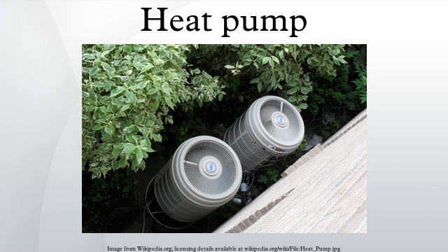Air source heat pumps are relatively easy and inexpensive to install and have therefore historically been the most widely used heat pump type. However, they suffer limitations due to their use of the outside air as a heat source. The higher temperature differential during periods of extreme cold leads to declining efficiency. In mild weather, COP may be around 4.0, while at temperatures below around 0 degrees Celsius an air source heat pump may still achieve a COP of 2.5. The average COP over seasonal variation is typically 2.5-2.8, with exceptional models able to exceed this in mild climates.